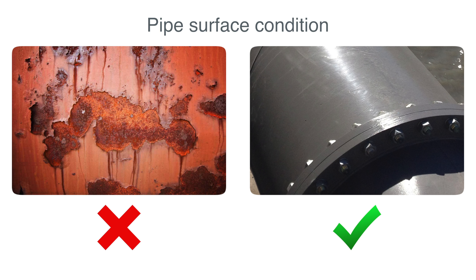Then make sure the pipe surface is clean without dust. The painting must be in good condition and well attached on the pipe, without blisters. If it is peeling off, remove it with a brush or scrapper, otherwise the air gap under the paint will stop the ultrasounds.